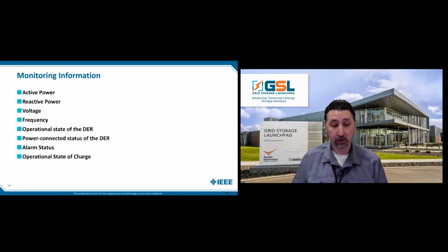Some of the information monitored includes active power, reactive power, voltage, frequency, and operational state of the DER. In context of 1547's base standard, the operational state of the DER is generalized—we are not device specific, definitely talking about agnostic. 1547.9 touches on the energy storage side of things, where operational state could include state of charge, but 1547 itself doesn't cover that. It's really looking at whether it's exporting, importing, or offline, not necessarily whether it's acting as a load or addressing energy storage specific capabilities. Other attributes include whether the device is power connected—online and connected to the system—alarm statuses, and operational state of charge.